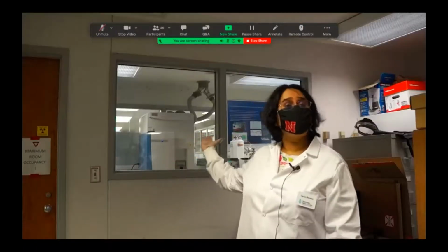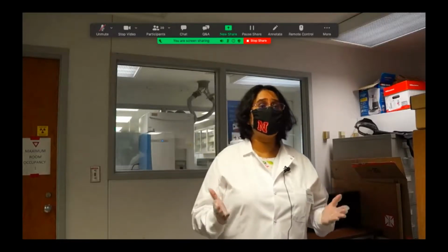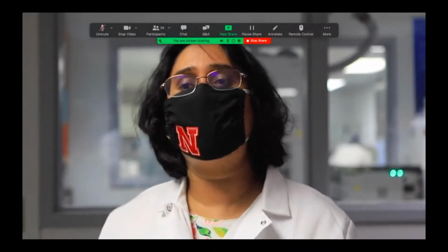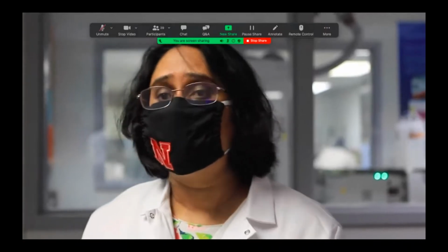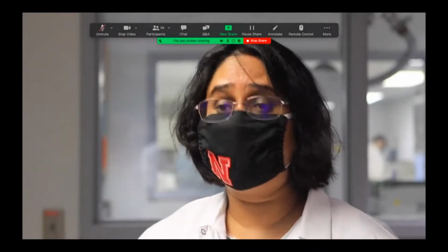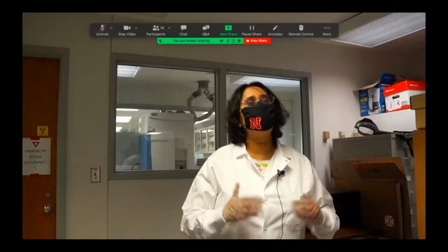This is the inductively coupled plasma mass spectrometer, or ICP-MS, that is used for measuring very low concentrations of elements like arsenic, selenium, uranium, lead, cadmium, manganese, and so many others. The sample is aerosolized and introduced into the plasma chamber. This enables the ICP-MS to measure the formation of charged ions through kinetic energy discrimination that removes interferences and makes it highly sensitive.